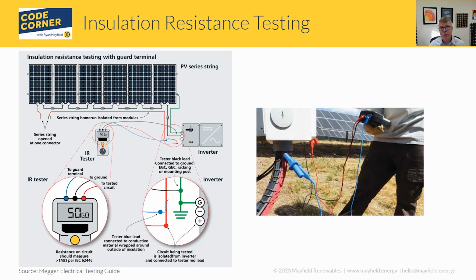And then the other thing I'd throw out there is that some of these handheld meters will have what's called a guard terminal. This is a really interesting phenomenon. If you can imagine, you're injecting that conductor with high voltage, and no insulation is perfect. There's no way for any insulation to be absolutely perfect.